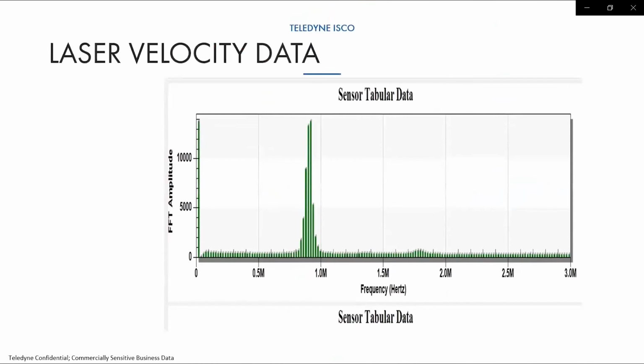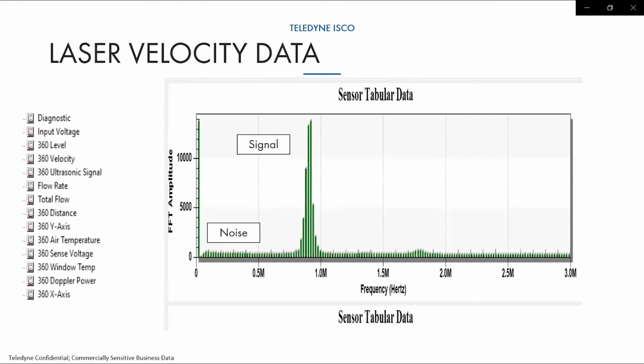Now here's what the diagnostics look like on a LaserFlow sensor. So when that laser is on for 2 seconds, it develops this curve, and this is the area under the curve. So when it takes those 5,000 readings, the more the readings agree with each other, the tighter this bell curve and the higher it's going to be. And so if we had a lot of turbulence and swirling water, like the poor ratio, you would end up seeing this signal being much lower and wider, indicating that there's swirling, possibly from debris in that channel. So again, you want to look at the historical data. When everything's first installed, I get this good signal, and all of a sudden it degrades. It gives me an idea where the noise is coming from, and then I can send crews out to resolve the problem.